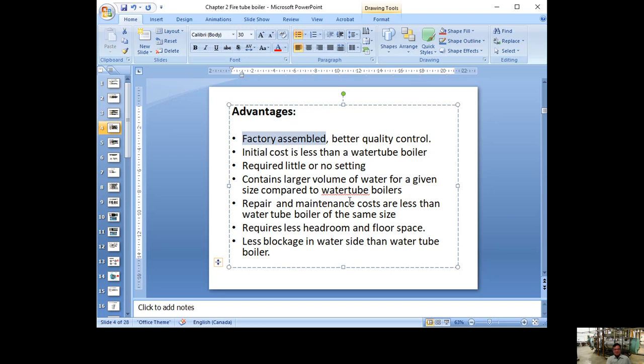Looking at the picture of the fire tube boiler, they are long but not very high, so your building doesn't need to be extra tall. A water tube boiler is oriented the other way and requires a much taller building. There is also less blockage on the water side because in a water tube boiler, the small two- to two-and-a-half-inch tubes can get blocked, especially at bends. In the fire tube boiler, the water is on the outside in a really large space, so blockage is not a serious problem.